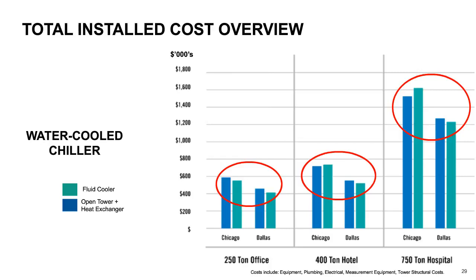We went back and looked at the numbers for Chicago, and what we found is that the cost of the glycol in the system, along with the slightly larger fluid cooler that's required when you're cooling glycol, because it's not quite as efficient as water, created an extra cost burden for the colder weather climates.